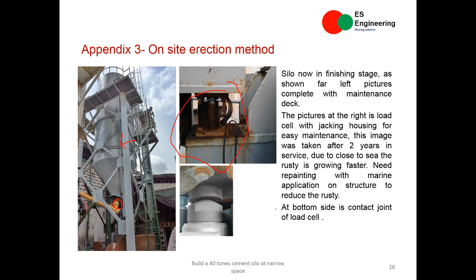Okay, we discussed the load cell. I ordered the load cells from the UK with a specific constraint that I don't want any mistakes during calibration. So I asked the load cell providers to provide me the load cells including the display, but they have to do lab calibration of the load cell and the display. So they have to take the load cell and the display I ordered, connect them together, and do lab calibration, usually using a press machine, let's say 1 ton, 3 ton, 4 ton, and so on.